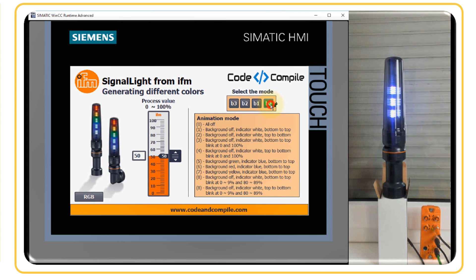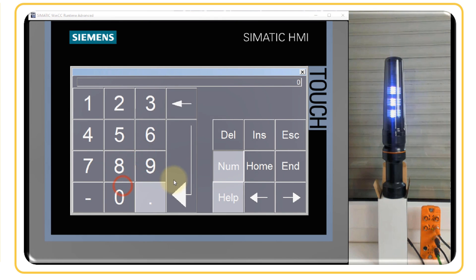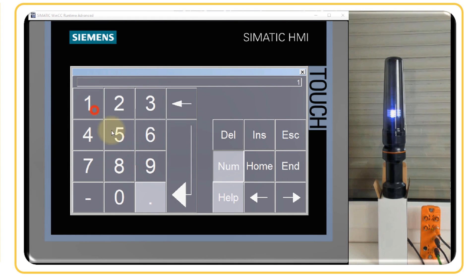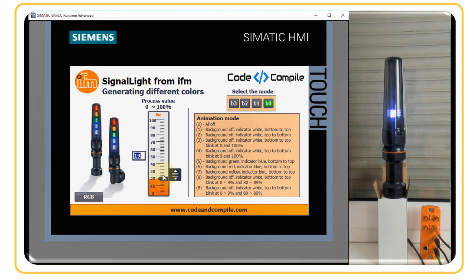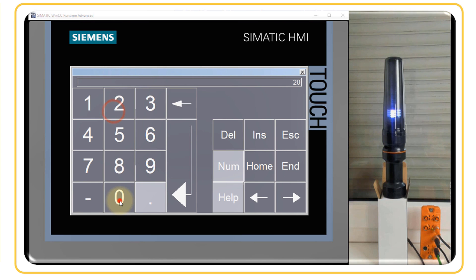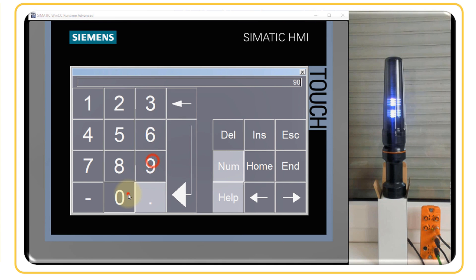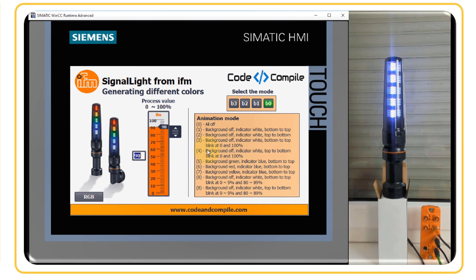Mode one: background off, indicator white, bottom to top. At 50 percent, three segments are on from bottom to top. The 100 percent analog range is divided across five segments of 20 percent each. At 0 percent, only one segment is on. From 0 to 19 percent, one segment is always energized. At 20 percent, the next segment turns on. At 90 percent, all segments are on.